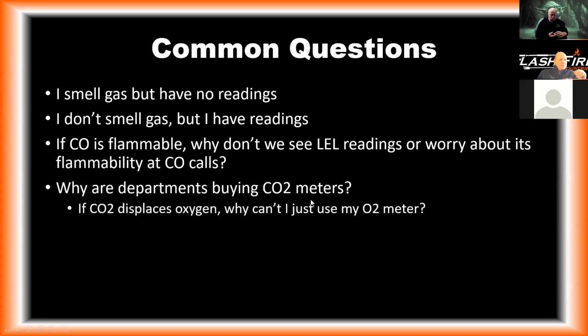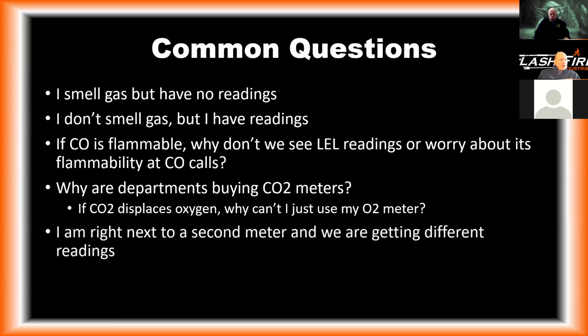We talked about CO2 meters being used a lot in fast food restaurants and whatnot, so CO2 systems are being used a lot more. The other place, a buddy of mine does a lot of HVAC refrigeration on the commercial level, and they're starting to transition a lot to carbon dioxide from ammonia. So this is something that we're going to start to see. And while carbon dioxide does displace the oxygen, it's right on the cusp of being more dangerous before you'll notice it on the O2 sensor. Carbon dioxide has an ionization potential, I believe, in the 12 range. So it's not going to show up on our PID meter.